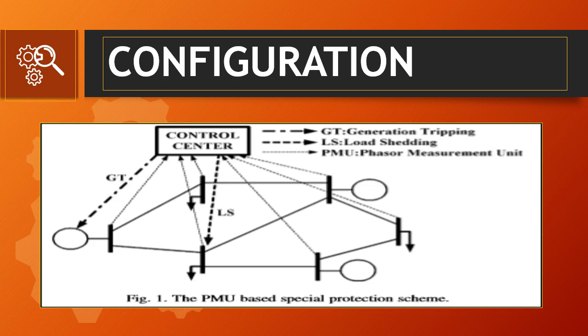The remedial control action consists of load shedding and generator tripping. The algorithm for determining the timing and amount of remedial control action is proposed relay setting limited equal area criterion. The following steps are proposed. Number 1, group generators swinging coherently and reduce system to an OMIB system. Number 2, estimate the parameters of OMIB system using real-time phasor measurements. Number 3, determine the timing and amount of remedial control action by relay setting limited equal area criterion, that is called EAC, the ACT method.